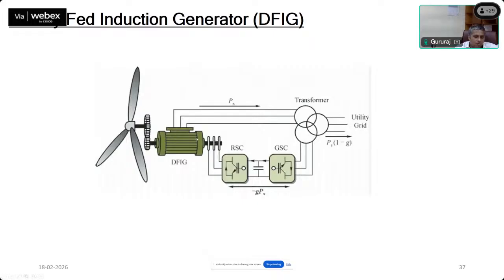because the fundamental requirement for grid synchronization is that the frequency should match. So how would this type of generator function then? What actually happens is, in real time, because these converters are very fast acting switches, this particular converter, which is the grid side converter, would borrow some power from the point of common coupling, or the utility for that matter, and feed it to this DC link capacitor. Now how much power it would pump depends upon the DC link voltage.